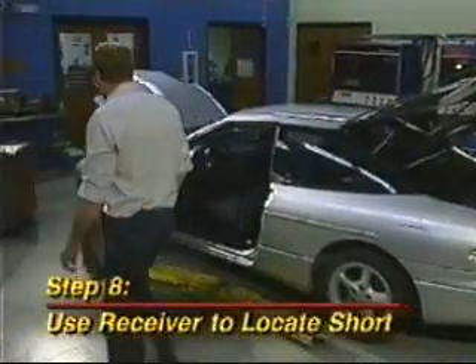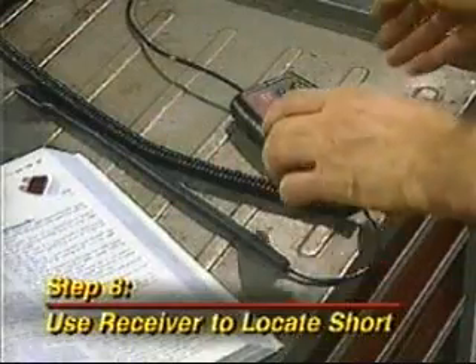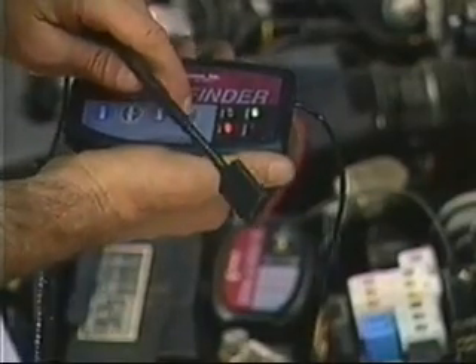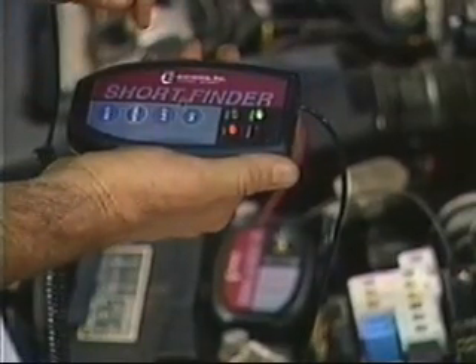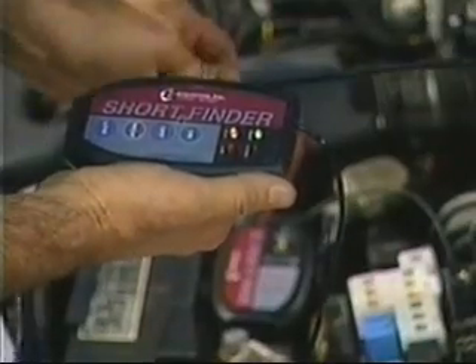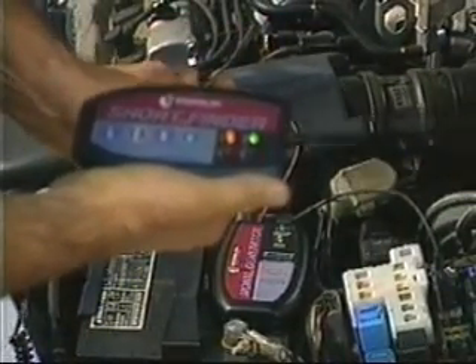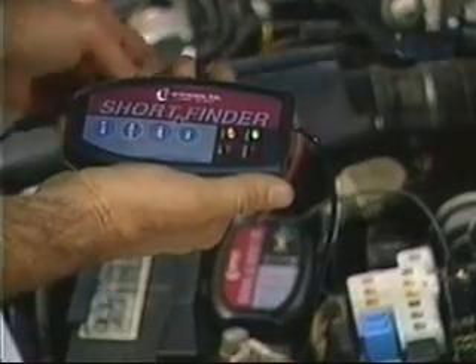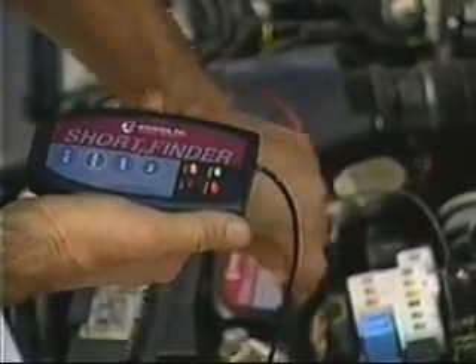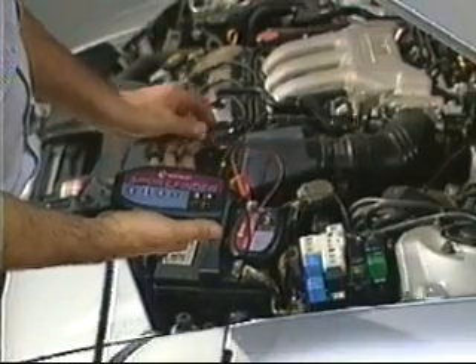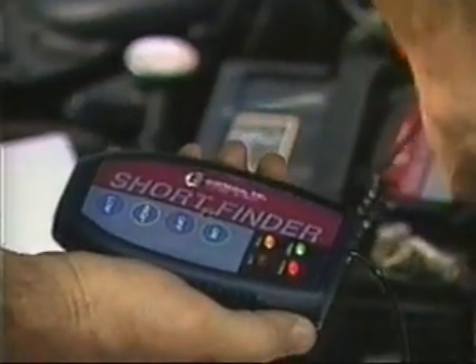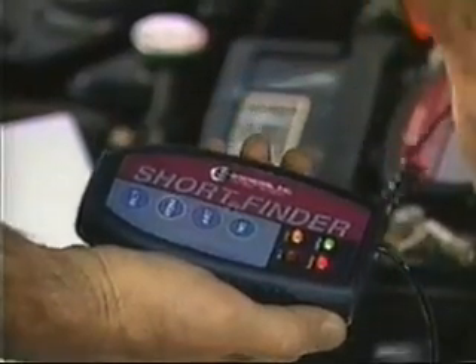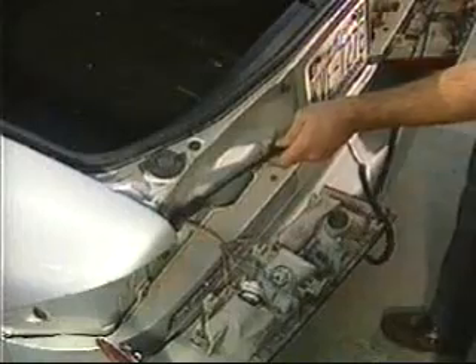Step 8 is to use the receiver to locate the short. To begin using the receiver, turn it on by pressing the power switch. The green light on the receiver will come on. Then set the sensitivity switch to high for the initial search. Hold the probe over the signal generator to verify that it is receiving a signal. Be sure to hold the probe at a right angle to the circuit so the receiver can pick up the signal properly. You should hear the signal tone, and the red light on the receiver should be lit. Starting from the signal generator, trace the wire harness of the circuit until the signal stops.